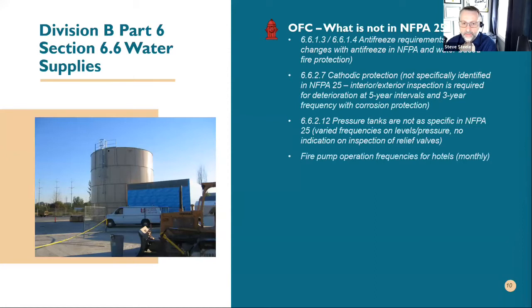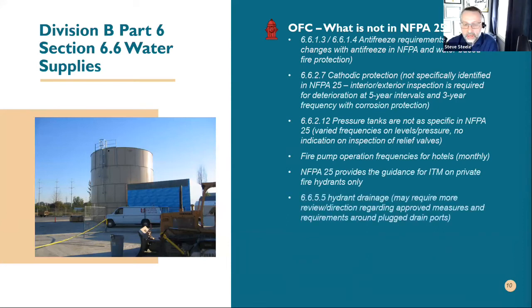Again, with the hotels, fire pump operation frequencies, this was longer, so it's not necessarily you're probably going to get more stringent, is that they had leniency for the operation or the run tests for churn on a monthly basis for hotels, obviously, whether that's for disruption or otherwise. And then NFPA 25, important note, the ITM for hydrants is guidance applied for private hydrants only. This does not cover municipal hydrants in that regard.